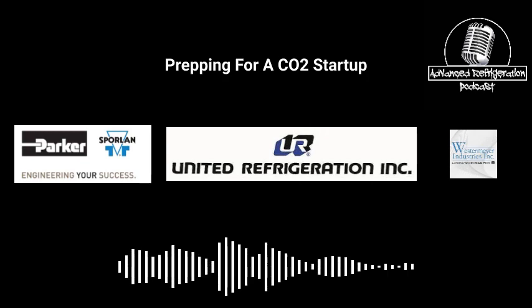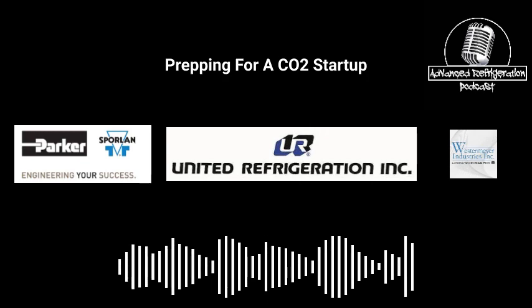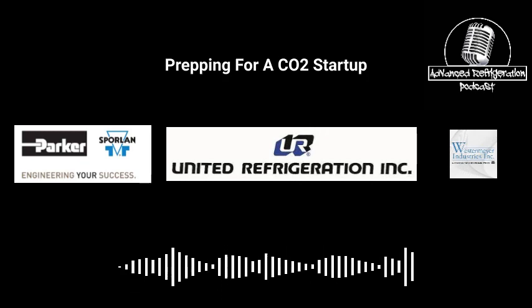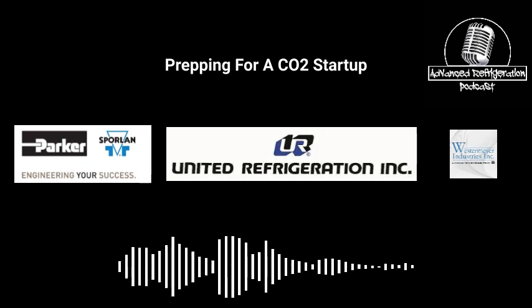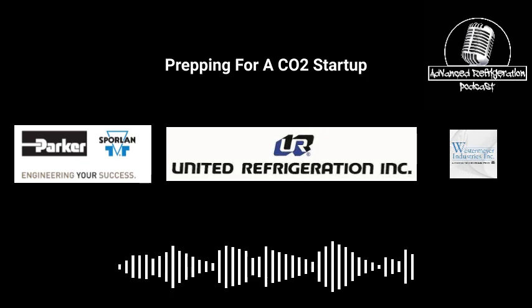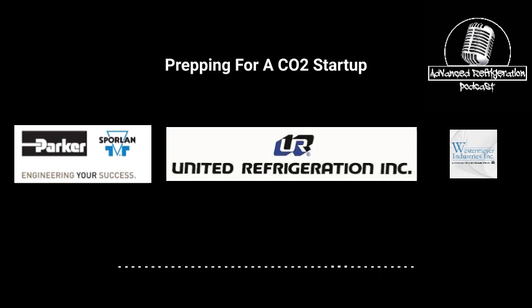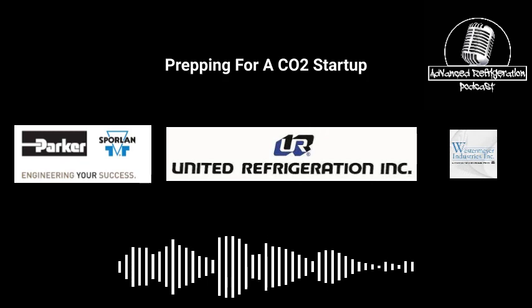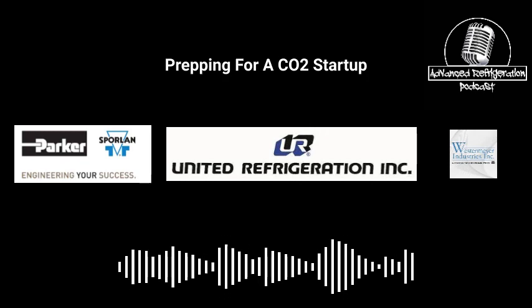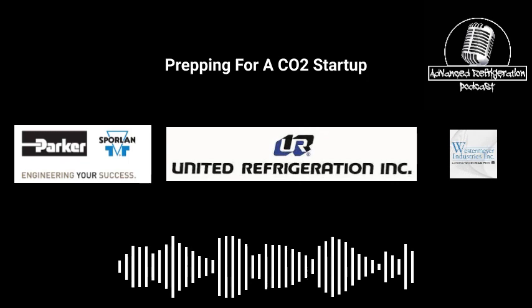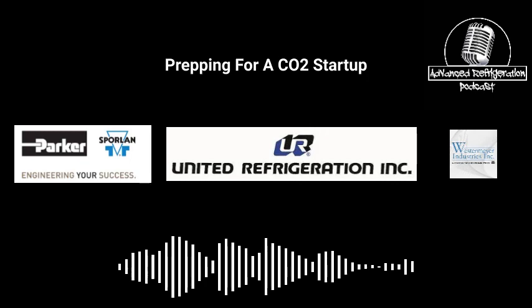Zero Zone's real good about this. They put a ball valve, then a 3/8 tap, then it goes through the dryer shell, then it goes into the store. So you feed the CO2 through there, and it goes through the dryer first, which is how it should. We've been filtering it off like a 163 dryer, and then we run it through the dryer into the case. The reason I feed it through the store is if you feed it in that flash tank, you're only getting like 70 to 80% of the CO2 out of those tanks.